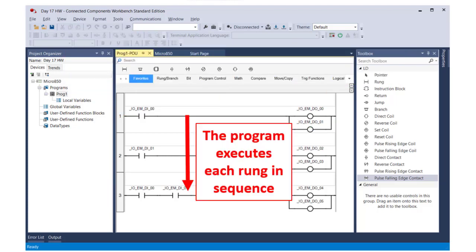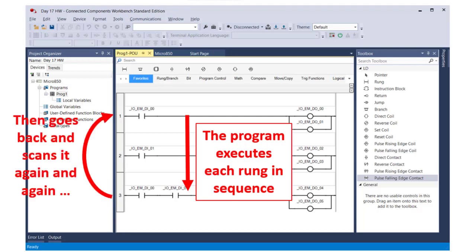The PLC executes each rung in the program in sequence from top to bottom, scanning inputs and making related changes to the outputs. Once it has scanned the entire program, it goes back to the beginning and scans the program rung by rung again, and again, and again. It does this very quickly, roughly 50 times a second if it's a simple program.